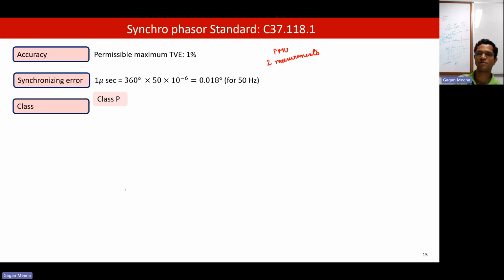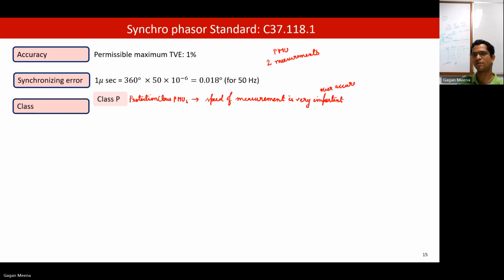The standard defines two types of PMUs. One is class P, the protection class PMUs. Here the main emphasis is on speed of measurement, which is very important instead of accuracy. We want less latency in measurement, and the maximum measurement latency here is 2 by fs, so 2 ts.